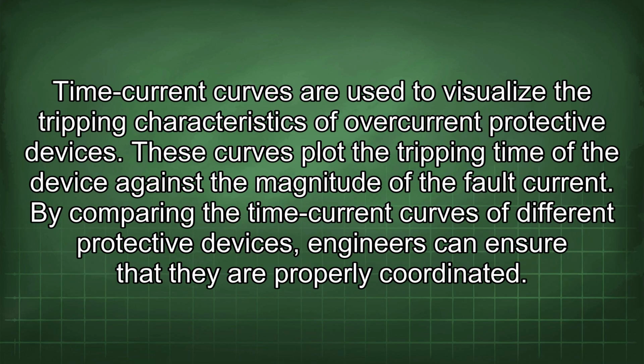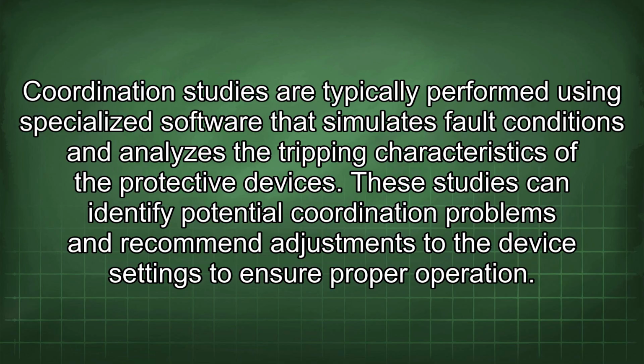Time current curves are used to visualize the tripping characteristics of overcurrent protective devices. These curves plot the tripping time of the device against the magnitude of the fault current. By comparing the time current curves of different protective devices, engineers can ensure that they are properly coordinated. Coordination studies are typically performed using specialized software that simulates fault conditions and analyzes the tripping characteristics of the protective devices. These studies can identify potential coordination problems and recommend adjustments to the device settings to ensure proper operation.